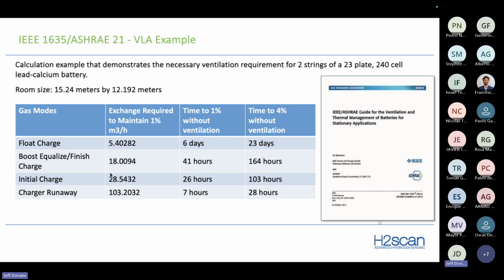And so we used a guide that has been out for several years. It's the IEEE ASHRAE guide for ventilation and thermal management of batteries for stationary applications. The nice thing about this document is that it takes into account the actual battery type, almost all the way down to the model number. They have a calculator that if you put the room size and the model number of the battery into it, it will give you the air exchange needed to maintain the 1%.